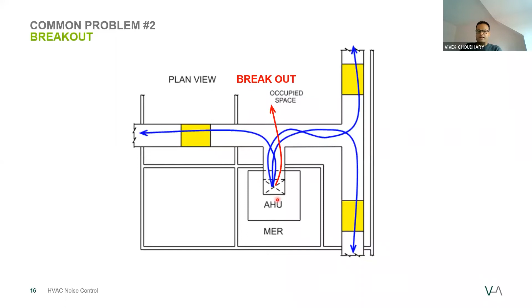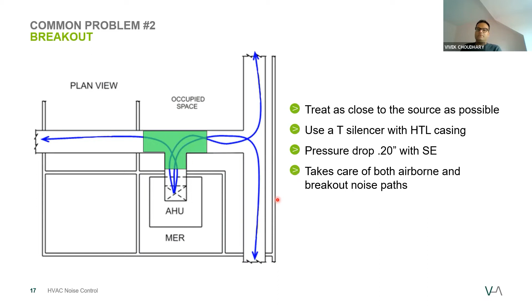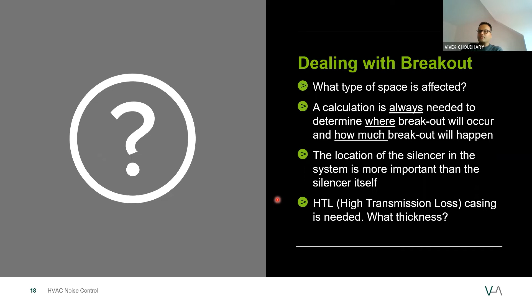What is the right solution? A T-shaped silencer, which will take care of not only the airborne noise, but also the duct-borne noise, with a better performance and a better pressure drop at the same time. To deal with the breakout, we need to look into what is the space affected by that breakout noise issue. And a calculation is always needed, which anybody from the Vibro-Acoustics team and Long Building team will be happy to help you guys calculate: is there a breakout issue? If there is a breakout issue, then we calculate how much it is. And then we provide an HTL casing silencer. Basically, HTL is a high transmission loss casing. It's a thicker gauge casing of the silencer to make sure noise is not going out from the silencer itself.